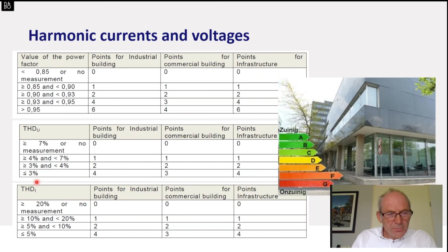Mostly the grid code already says you should have a power factor of 0.85 or more. So when that's not the case, of course you don't get any points, but when you have a very high power factor, you get the highest level of points. There's also one for total harmonic distortion in the current. When you can reduce the harmonic distortion in the current, you get more points, so a more efficient installation. And there's also the case for the total harmonic distortion in the voltage. One could discuss this a little bit, because you already have a harmonic background distortion in your voltage and you are not solely responsible for the harmonic distortion in the voltage. But that's how it is in the standard at this moment.